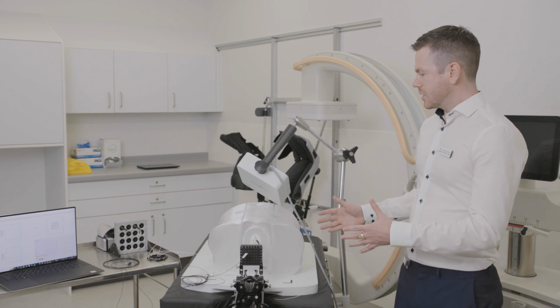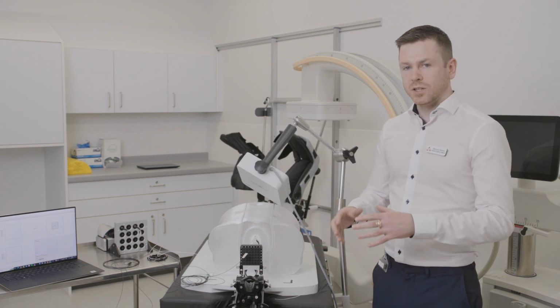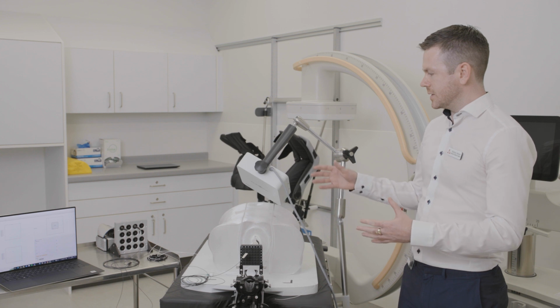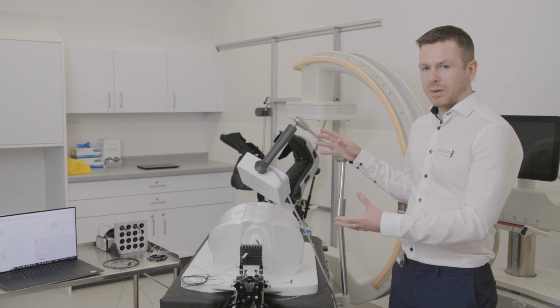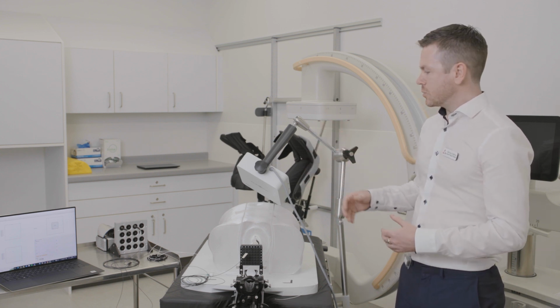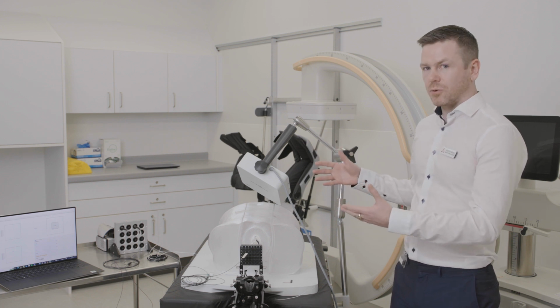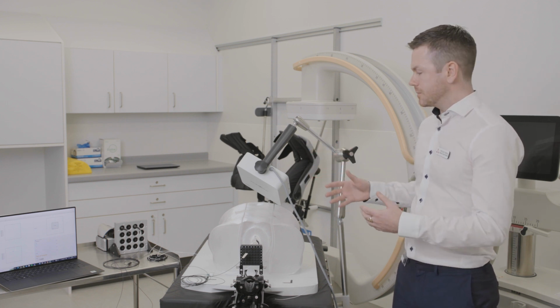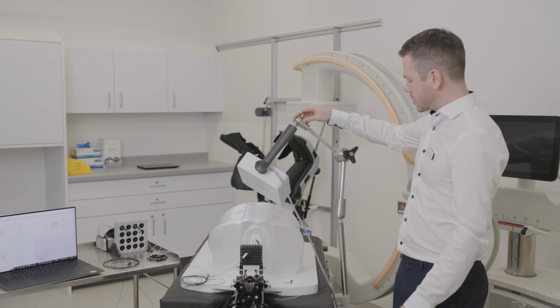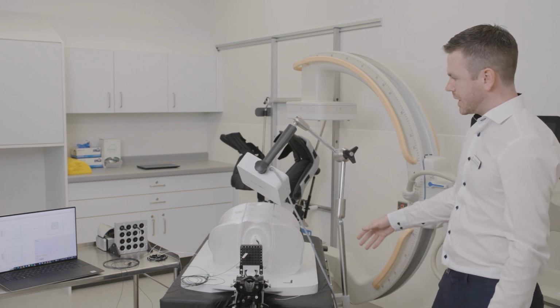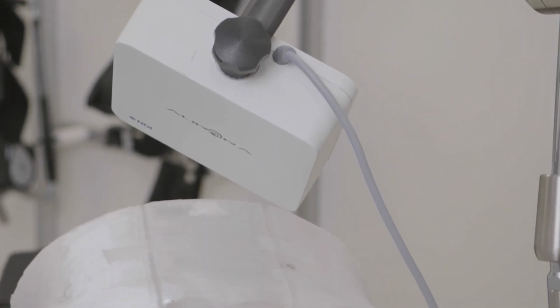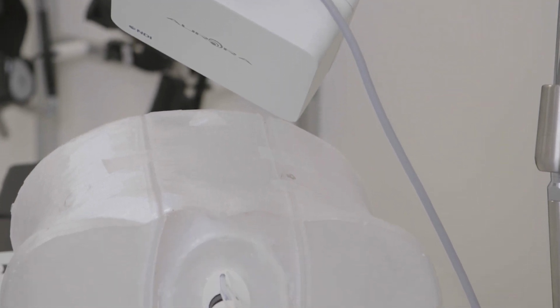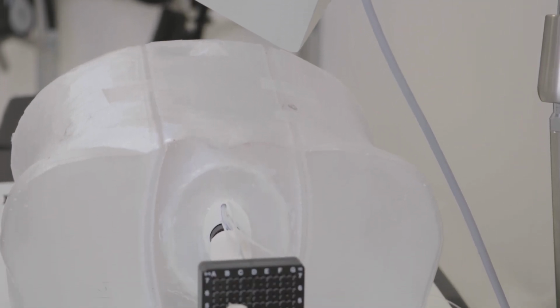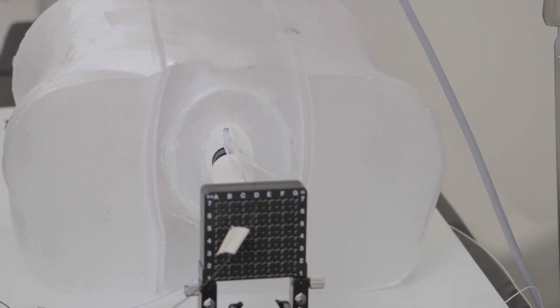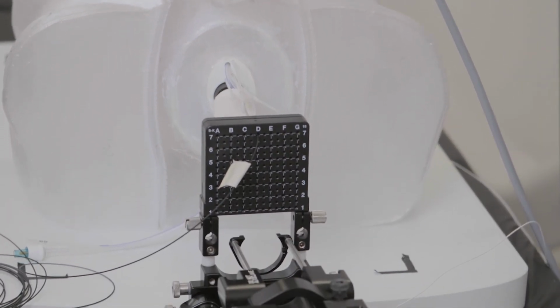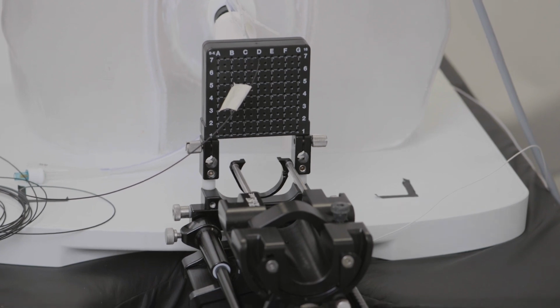Okay, so what we have here is another key component of the overall Origin system. This is an example of our electromagnetic tracking system. And we have two different options here for your electromagnetic field generator. This particular one here, which is mounted on an arm on the side of the bed, is called the planar field generator, and it will be positioned over the abdominal region of a patient for a typical low dose rate prostate brachytherapy procedure, or indeed a high dose rate gynecological procedure.